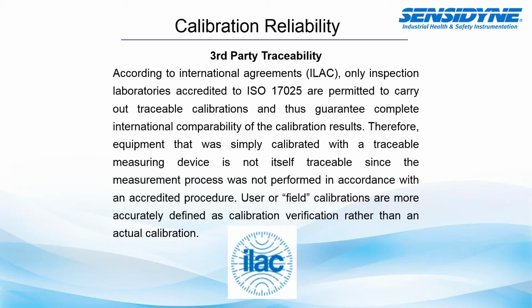Therefore, equipment that was simply calibrated with a traceable measuring device is not itself traceable, since the measurement process was not performed in accordance with an accredited procedure. So user or field calibrations are more accurately defined as a calibration verification rather than an actual calibration. So let me break this down. There's a lot of technical jargon that I just went over, but I just wanted to distinguish when a field calibration is performed with the calibrator that is used in the field. That is a calibration verification to make sure that the unit that you're calibrating, the air sampling pump, conforms within a certain degree of the calibrator. However, that calibrator itself, in order to be certified calibrated, needs to have that traceability back to that NIST standard.